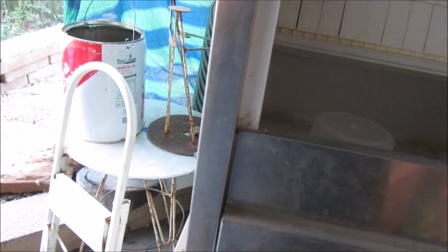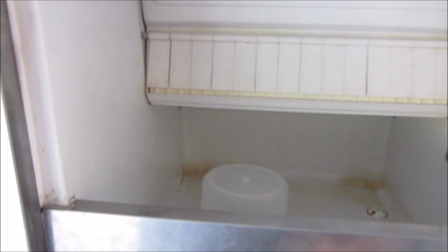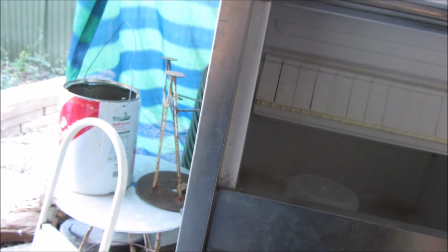Shouldn't be so complicated. As I said, it's got to build up ice. It gets just cold enough and it senses and starts the timer to dump the ice when it's finished. But what it's actually doing is not turning the timer on when it's cold enough, and it just sits there until all the water in here freezes and it cavitates the pump dry.